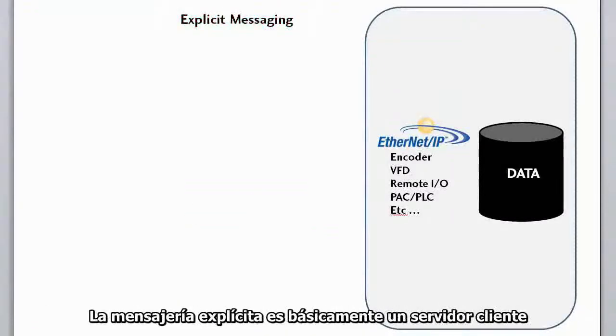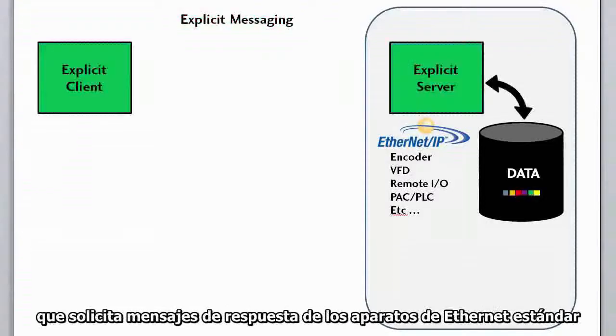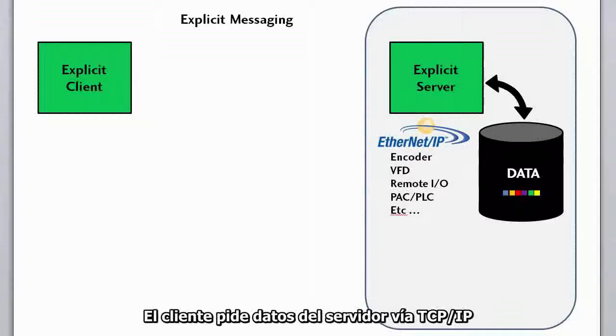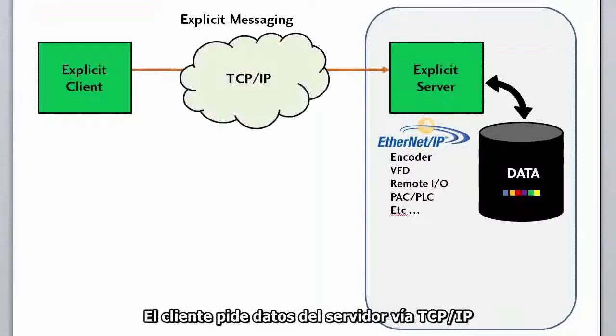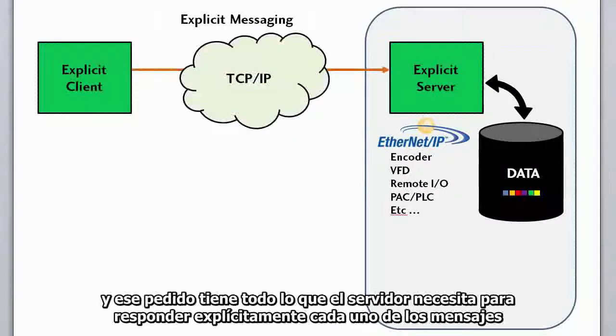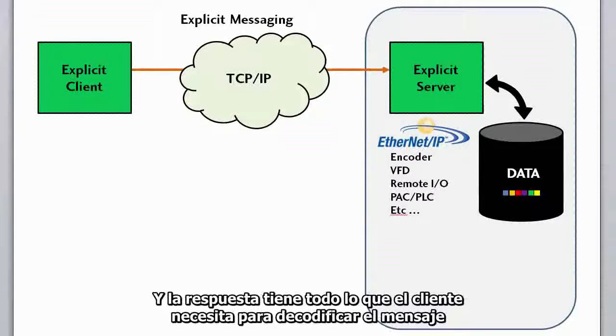Explicit messaging is basically the same client-server request-reply messaging that you find in standard Ethernet devices. The client requests stuff from the server via TCP/IP, and that request has everything the server needs to respond explicitly built into each and every message. And the response has everything the client needs to decode the message.